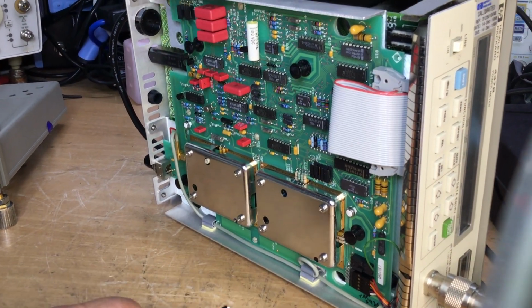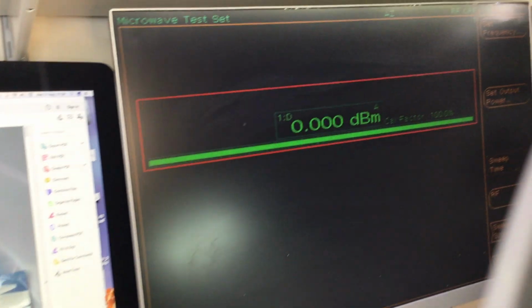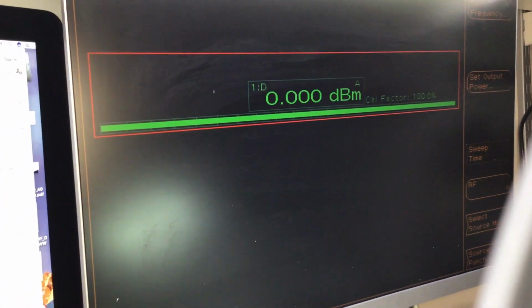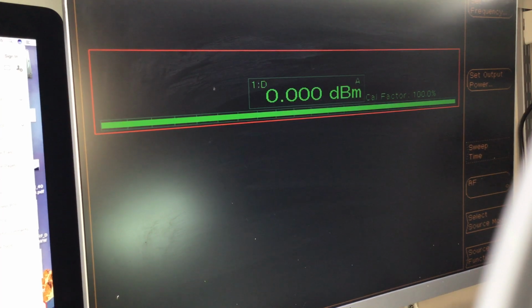Right, so we've removed the trimming tool now, we've let it settle. It's been like that now for several minutes at 0 dBm. So it's just settling time, that's all. When you put a potentiometer on, any slight adjustment or slight tapping of that, just putting pressure on it with the trimming tool, is enough to get it to start moving. But as you can see there, we're fairly stable now at 0 dBm. So I think we'll put the lid back on, and that's the meter calibrated.